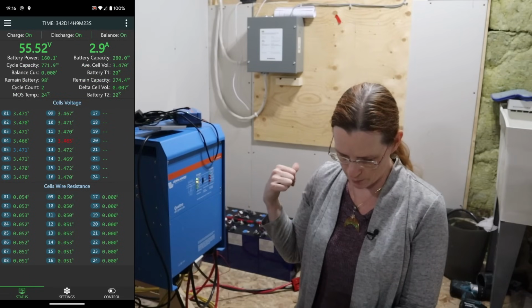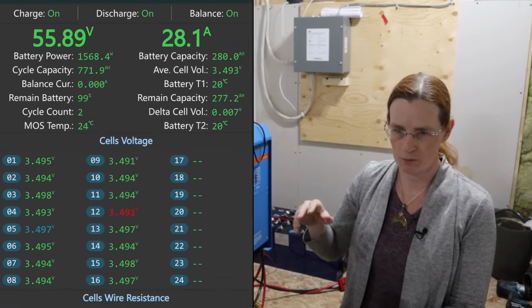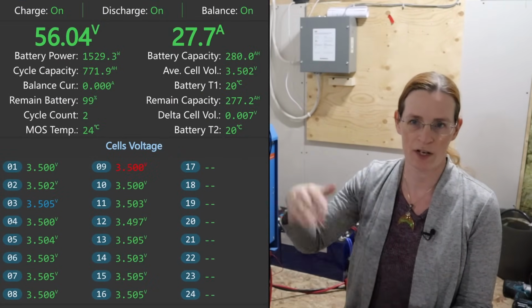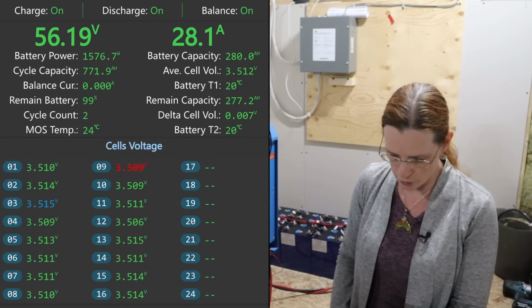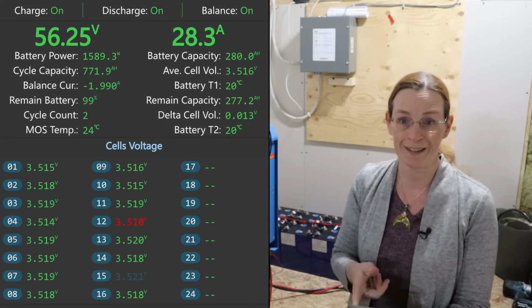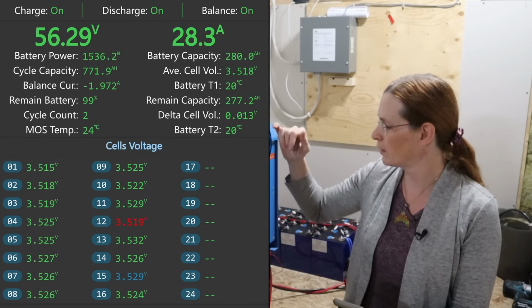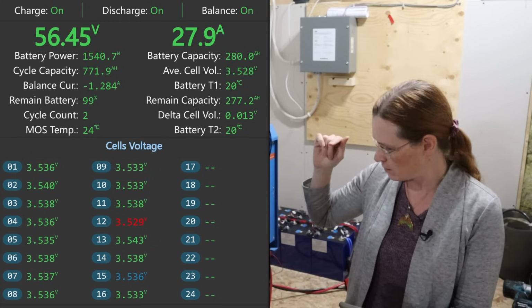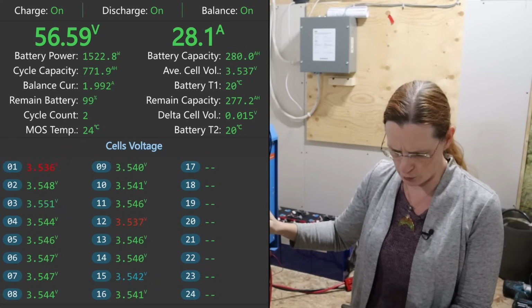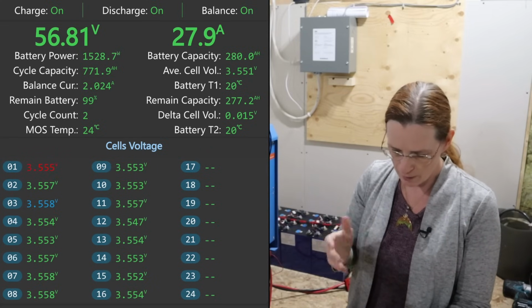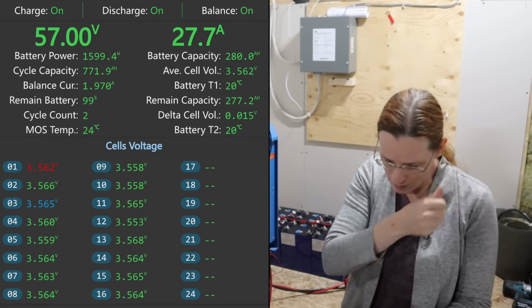Oh, I closed the screen. So now the voltage should jump up, and it'll throw a little bit of a charge in, but it's so close to the top that I suspect it's going to go into the overvoltage disconnect fairly shortly. When it does, I'm going to reconnect the Quattro and see if I can configure it for a higher float voltage, because they are so balanced, the delta at this point is 0.015.